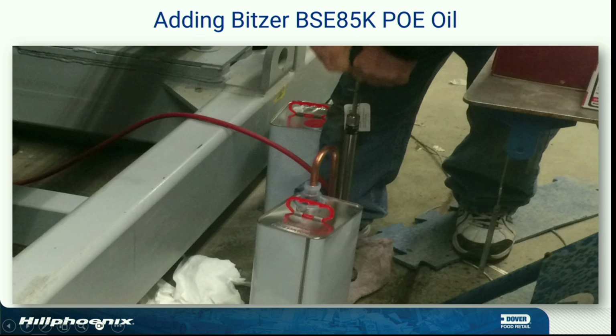When that oil hit that valve plate and went up to the gasket, it blew the gasket off of the discharge valve. Yes, sir. It happened to me 8 months later. What I did was I turned the farthest case on and let the rack start and just let it run for an hour like that. On and off, on and off. But that oil went out, came back, because it's going to come back fast with CO2. It's very miscible. Okay? Everybody knows what miscible means, right? The oil molecules and the CO2 molecules are very attracted to each other, and they go hand in hand up the system and out the system. Okay?